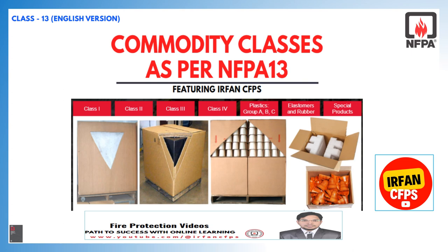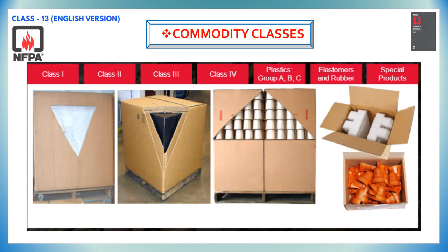Hello everyone, welcome to Irfan CFPS YouTube channel. In today's class we shall go through commodity classifications as per NFPA 13. Let's begin our class with types of commodity classifications. Commodity classifications are broken down into class 1 through class 4 and group A through group C plastics, with class 1 being the lowest hazard level and group A expanded plastics being the highest hazard level.